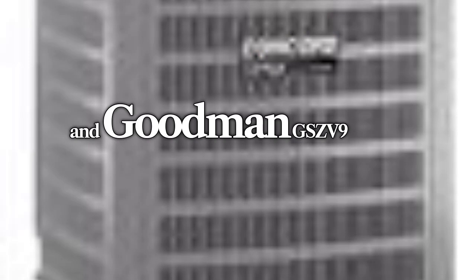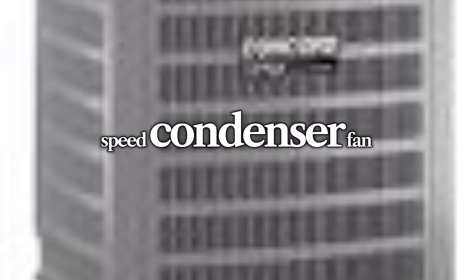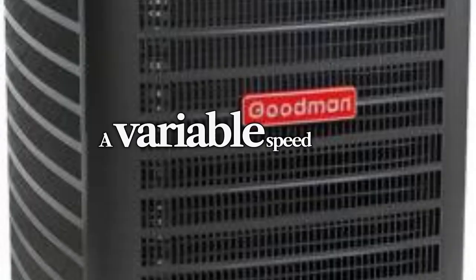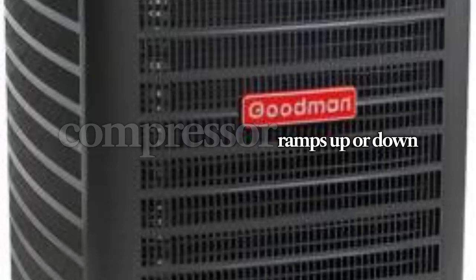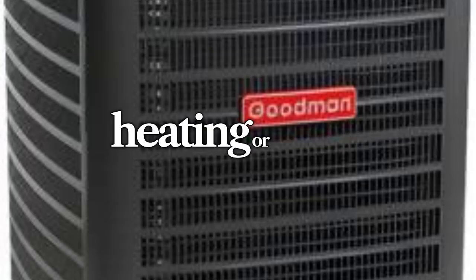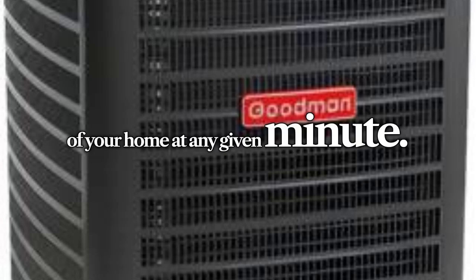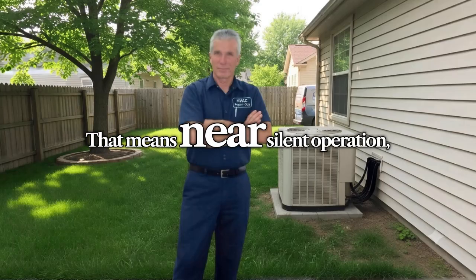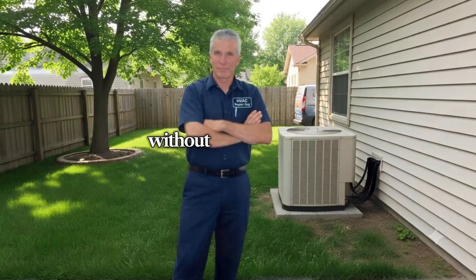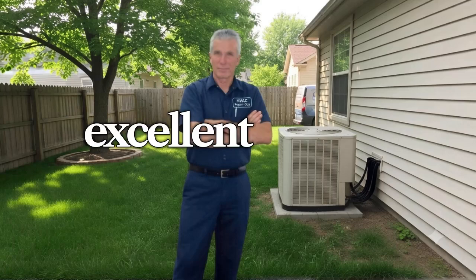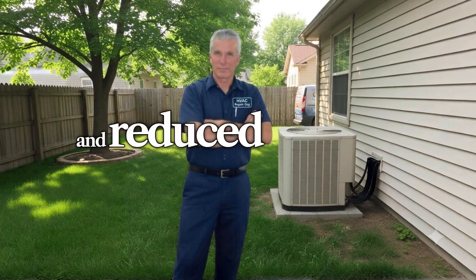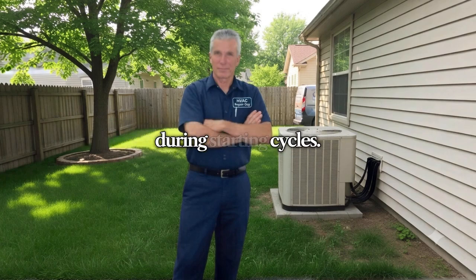Both the Concord 7HP19V and Goodman GSZV9 feature variable speed compressors and variable speed condenser fan motors. A variable speed inverter compressor ramps up or down incrementally to match the exact heating or cooling load of your home at any given minute. That means near-silent operation, precise temperature control without hot or cold swings, excellent dehumidification, and reduced mechanical stress during starting cycles.